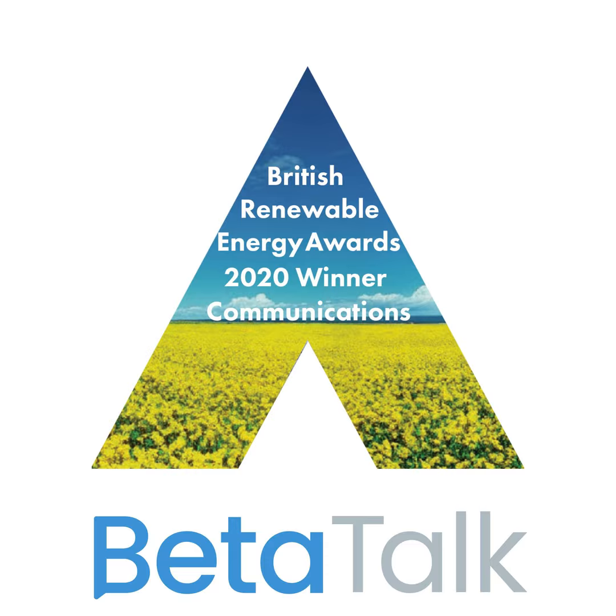But I do question sometimes if you really need it. We did install on quite a few systems, and we do install because some manufacturers state they need X and Y. So, for example, we only fit one on the return, because my logic is that it's basically there to stop the water freezing that condenser and causing a failure on that condenser. So if you've got one valve on there, yes, potentially you might say, oh, you're not going to have an air intake, so the water's not going to drain out. But actually, I just want that to open, because if it starts freezing, it's going to go the path of least resistance. It's going to be easier to go out that hole than it is to freeze in the heat exchanger, and that's my logic. Now, someone can probably say if that's wrong or right.